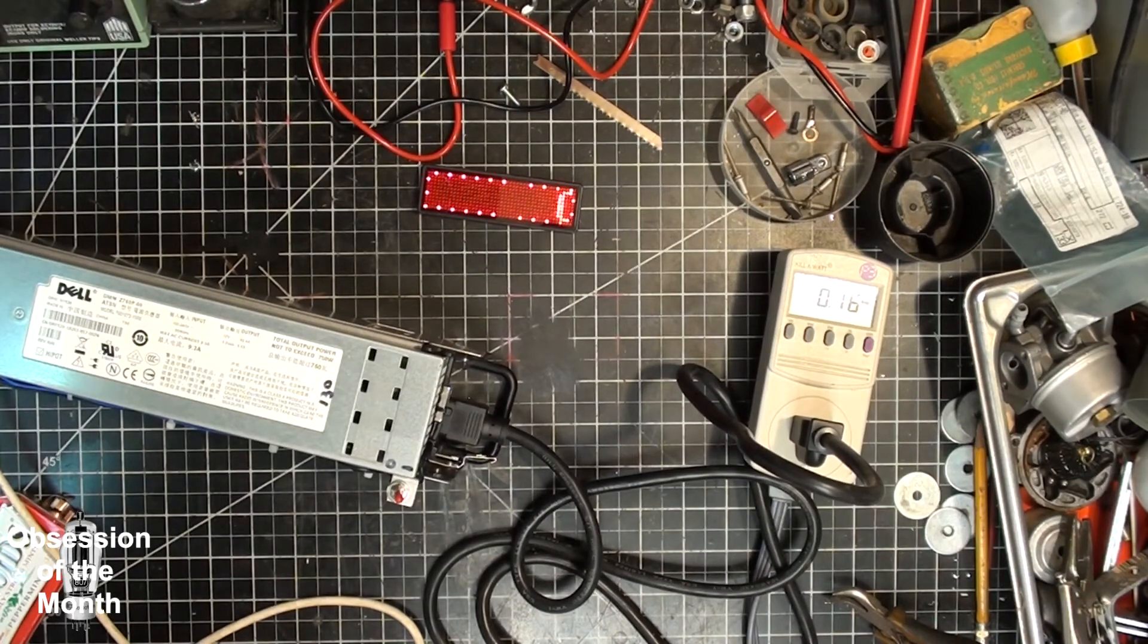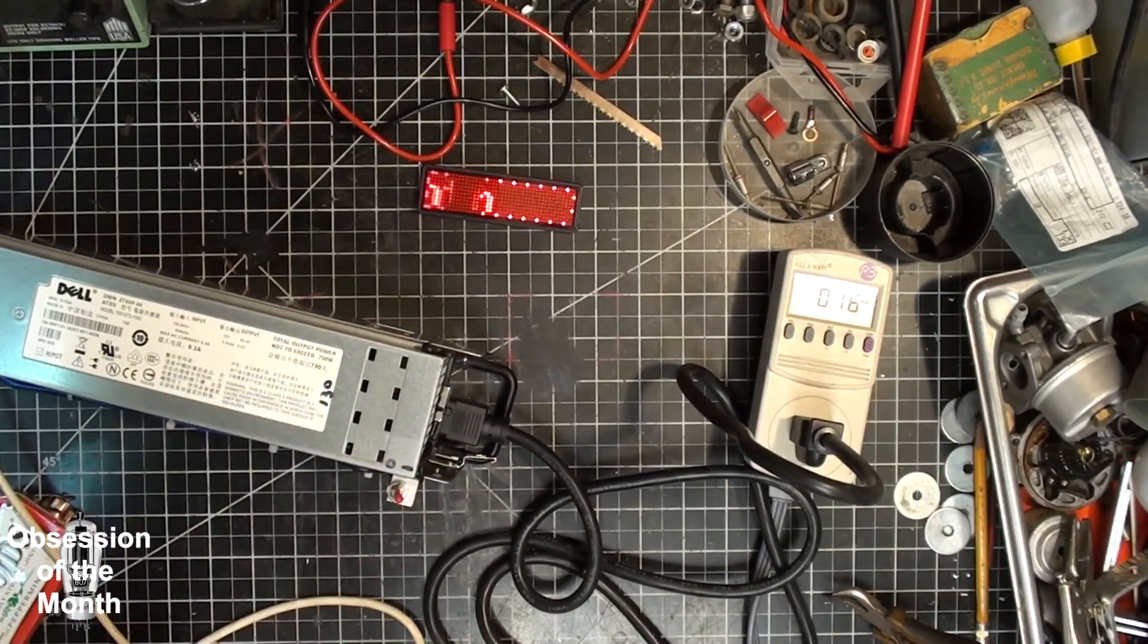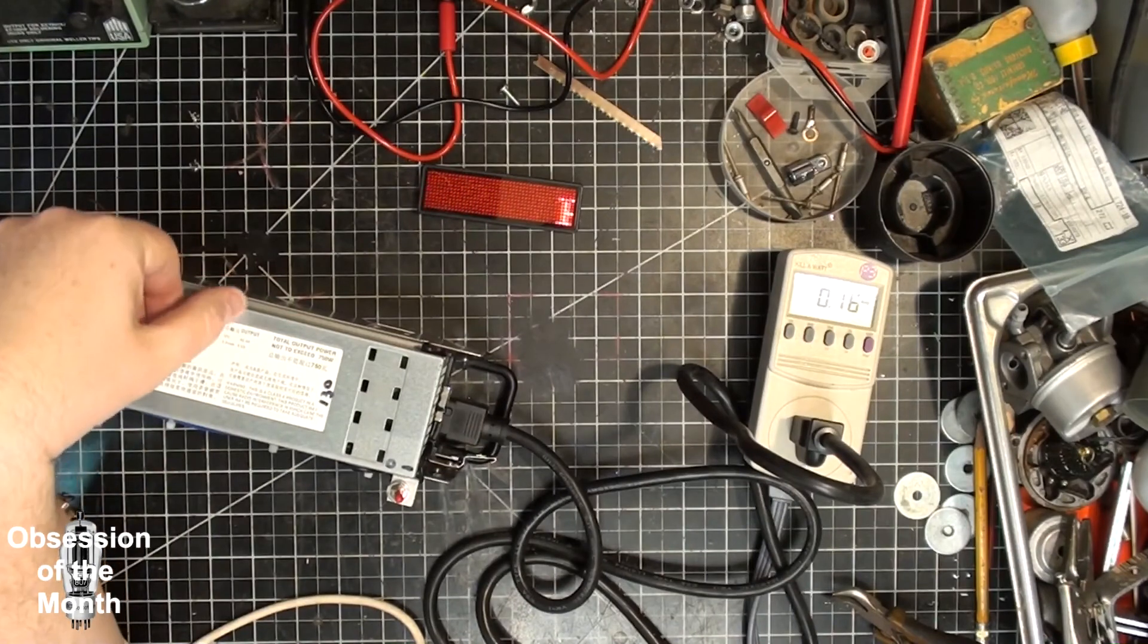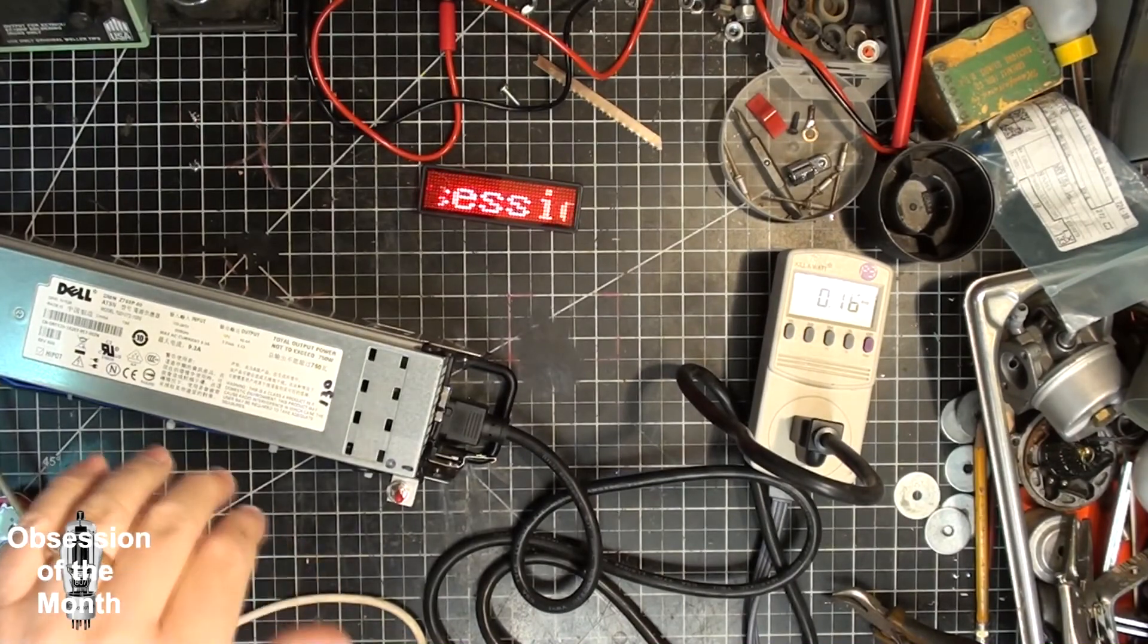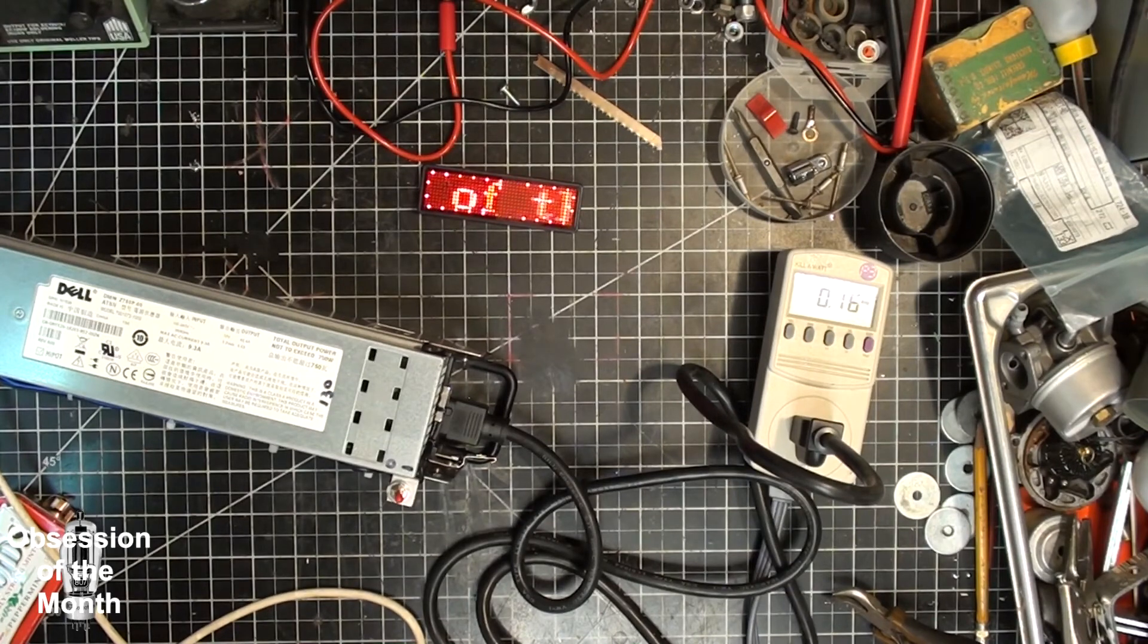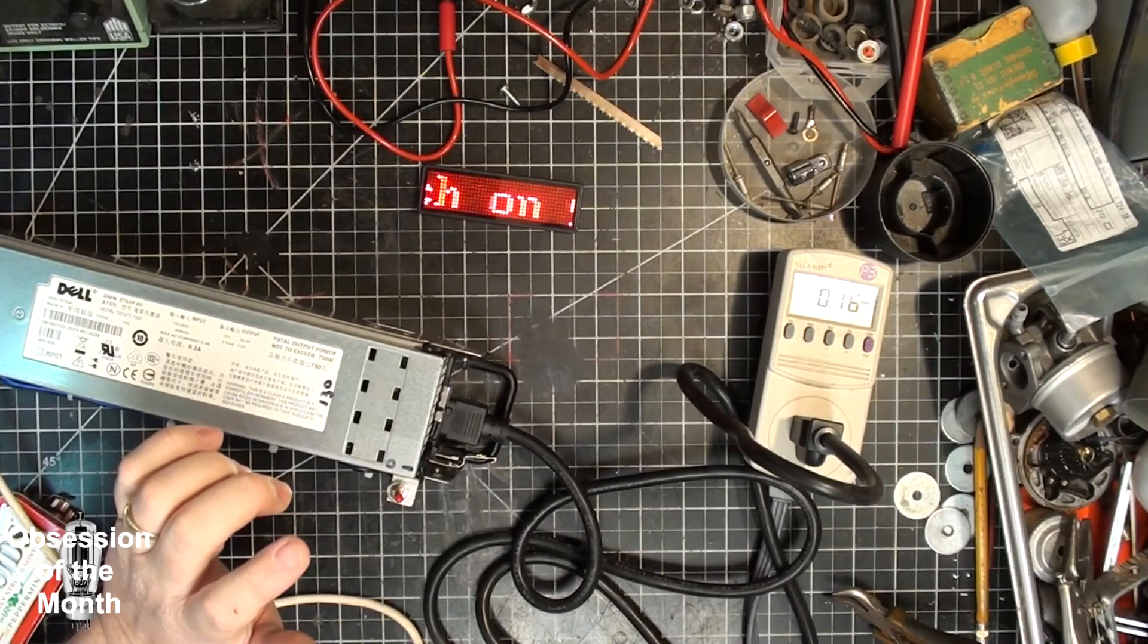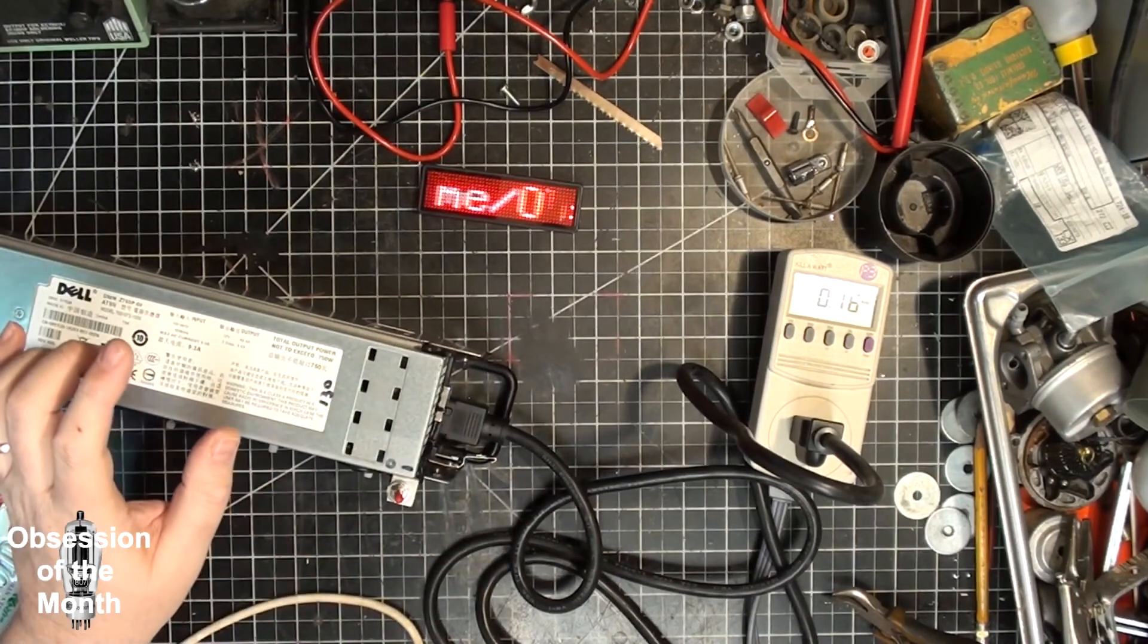Now, the thing about this is, this is a 114 degrees Fahrenheit normally closed switch. And it may be too high of a temperature, because the temperature inside this thing is always going to be hotter than the air coming out of it. And so, it might require something lower like a 40 C or a 35 C, which would be 95 to 104 degrees. Because the temperature inside here could be 120, 130, 140 degrees, but the air coming out the back might be 110.